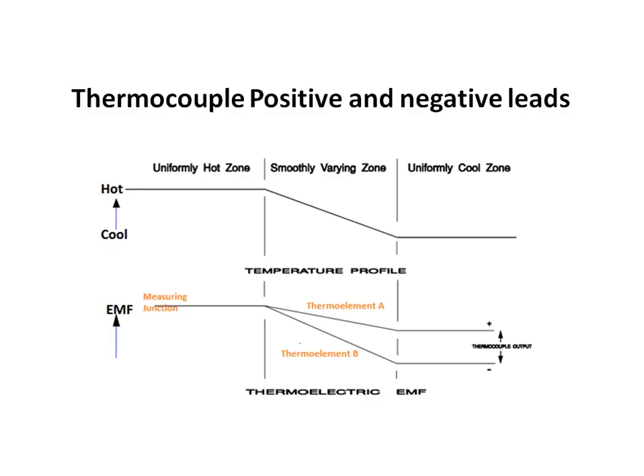In a thermocouple, thermoelement A generates an EMF depending on its Seebeck coefficient, and thermoelement B generates another EMF depending on its Seebeck coefficient. The thermocouple output is the EMF measured between these two thermoelements. For the best thermocouple performance, thermoelement A should have the highest positive Seebeck coefficient and thermoelement B should have the highest negative Seebeck coefficient.